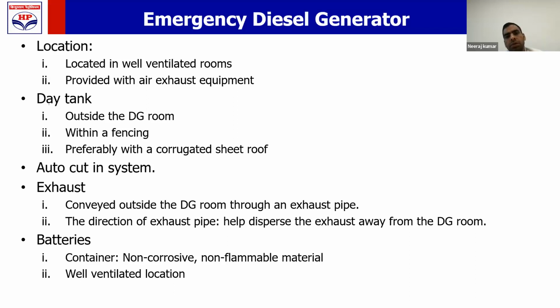Now let us talk about the emergency diesel generator. What we need to take care of for fire prevention in diesel generator installations, EDG. First is their location. How and where should the EDG be located? EDG should be located in a well-ventilated room. You should not put an EDG in an open area. It should be in a well-ventilated room with exhaust fans, like provided in the CPP of Mumbai Refinery. Provided with exhaust equipment means that an exhaust fan should be installed in that.